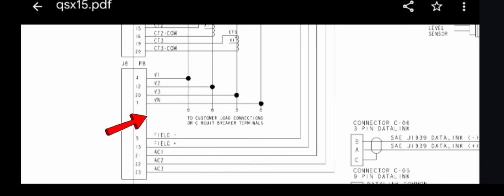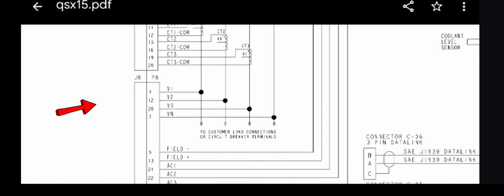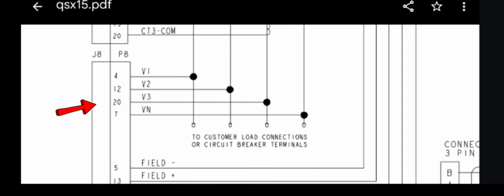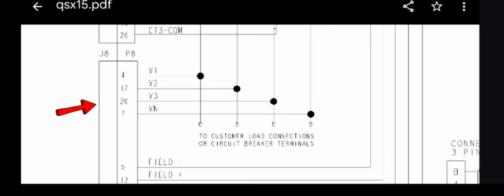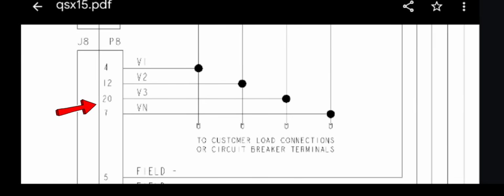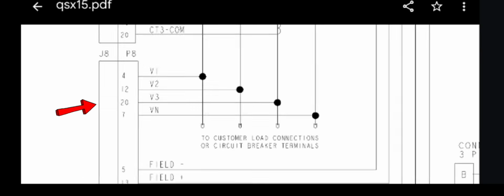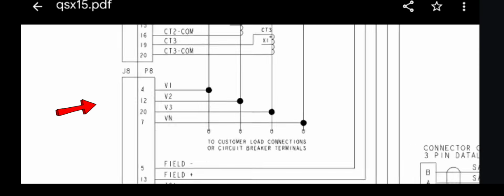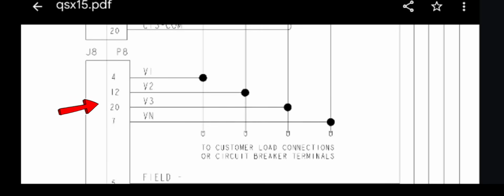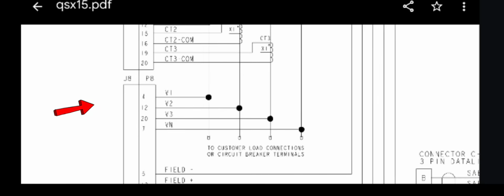After that, as you can see, we also have J8. As you can see, we have three phases and one neutral. J8 connects with the P8 connector, with pin numbers 4, 12, 20 and 7. As you can see, V1 means line 1, V2, V3, and also Vn for neutral. This 4-wire set is coming from the alternator, 3 phases and 1 neutral, into this PCC connector J8 and P8.